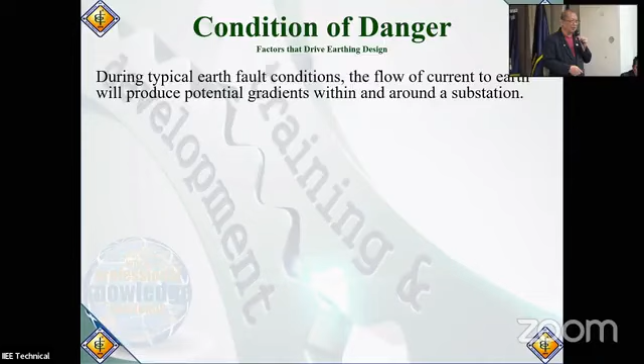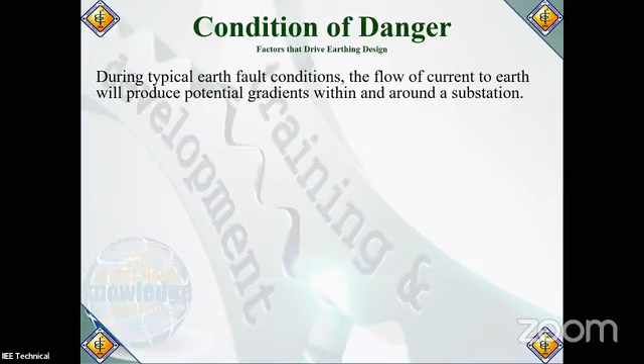Okay, so I would like to proceed. What are the factors that drive earthing design? First, we must review what are the conditions of danger. During typical fault conditions, the flow of current to earth will produce a potential gradient within and around the substation - pa sinasabi ko doon. I maybe have to change that into a power system, kasi wherever you are in the whole power system, ganun din ang nangyayari. Whether you're in a substation or within an ordinary power system environment, during a fault condition it produces potential gradients or potential differences in the different parts of the system, depende kung gaano kaganda ang earthing system mo.